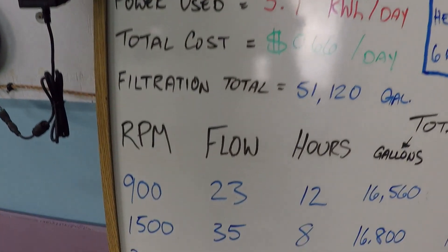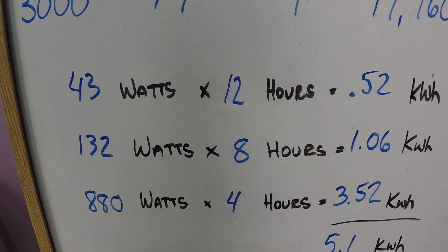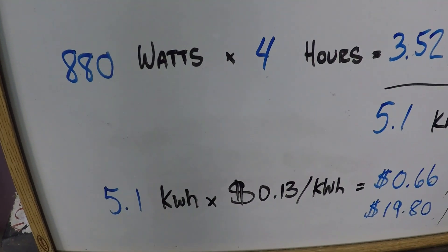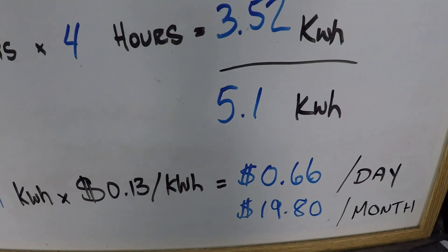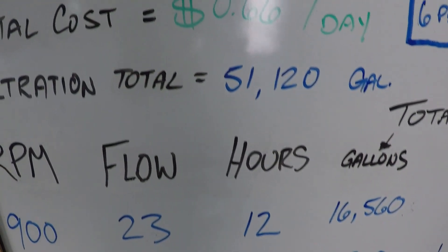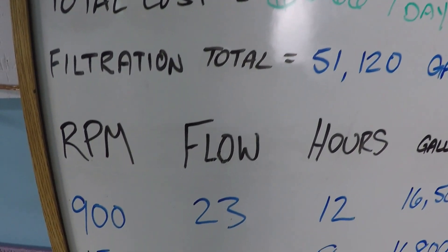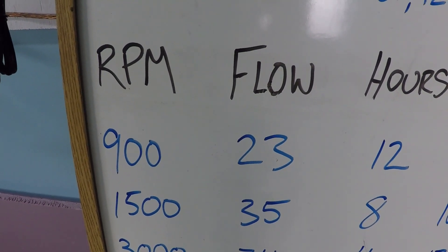Looking at these numbers, this is the power calculation for a total of 5.1 kilowatt hours over 24 hours. The nationwide average is 13 cents per kilowatt hour, and that's going to be about 66 cents per day — about 20 bucks per month. Which is pretty impressive considering you're getting over 50,000 gallons a day of filtered water, and the lowest flow rate during the day is 23 gallons per minute.